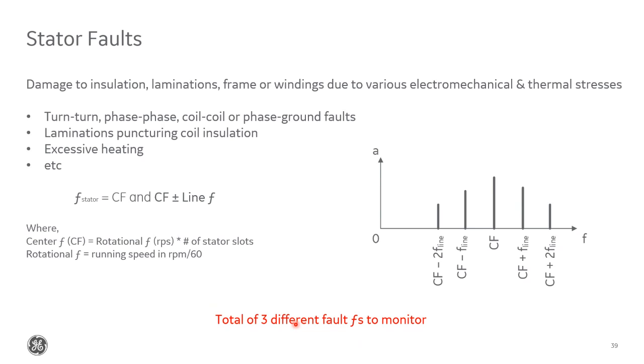The second type of issue we can detect with ESA are stator faults. That'd be any damage at all to the insulation, laminations, the frame, or the windings. And you see the predicted fault frequency formula here. Again, this calculation has been updated. Here we take into account the center frequency, which is the rotational frequency multiplied by the number of stator slots, which is from the motor data sheet. Then we plus or minus the line frequency to give us a total number of fault frequencies of 3. So we're looking at the center frequency and then the center frequency plus or minus the line frequency. So we have this one here and then either side here.